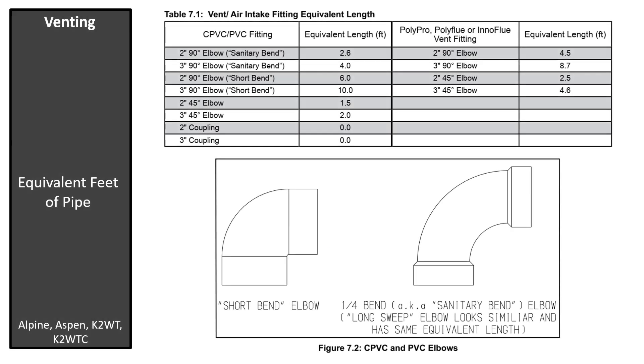The vent length shown in the charts is a total of the equivalent feet of pipe of all the fittings added to the length of straight pipe. Compare the result to the vent charts under the venting section in the I&O manual.